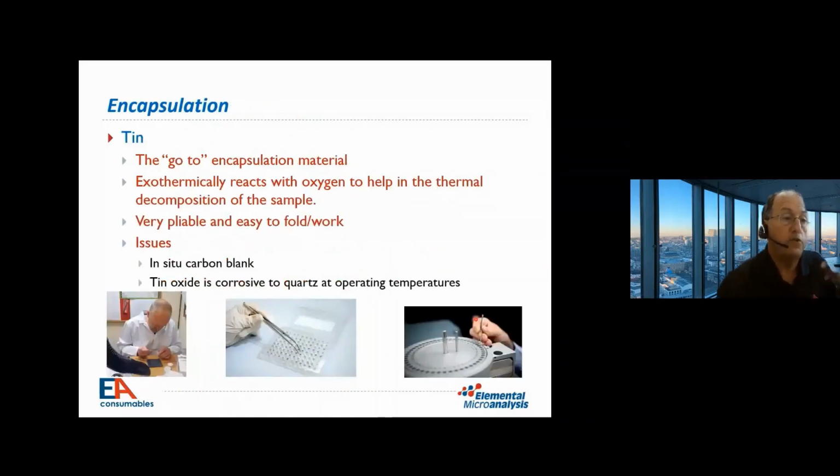Tin is the go-to capsule material. As we mentioned previously, it exothermally reacts with oxygen to help in the thermal decomposition of the sample. It's easy to work with. It doesn't have a zero carbon blank, and the tin oxide is corrosive to quartz at operating temperatures. So there's always compromises with everything you choose.